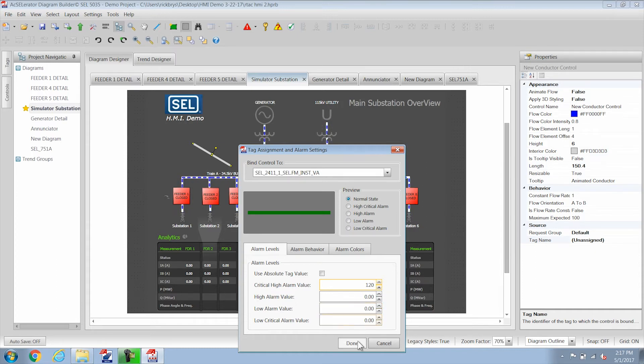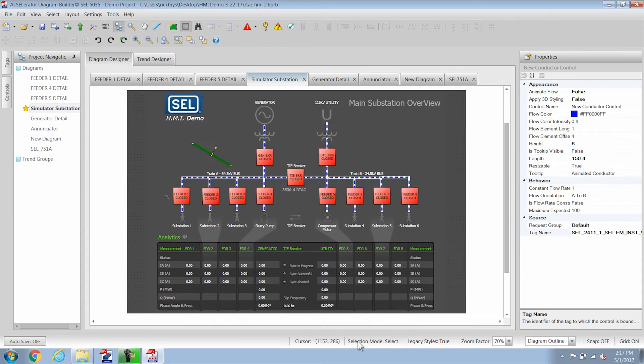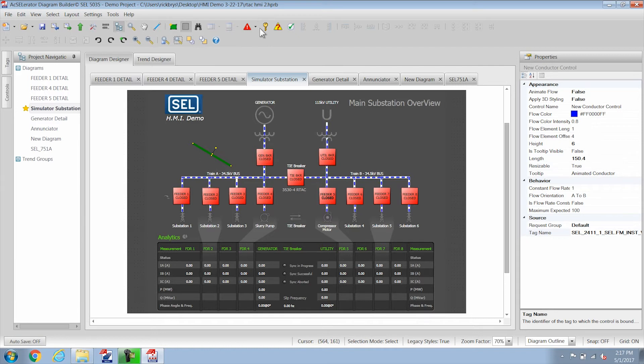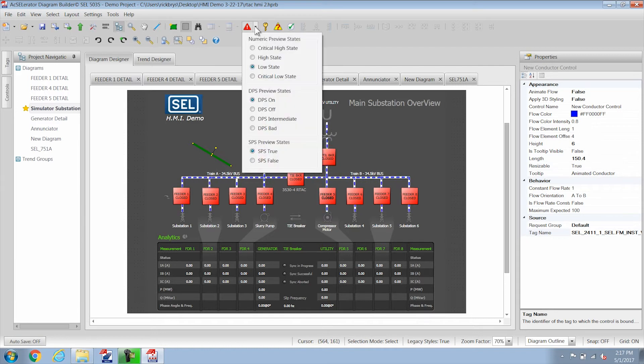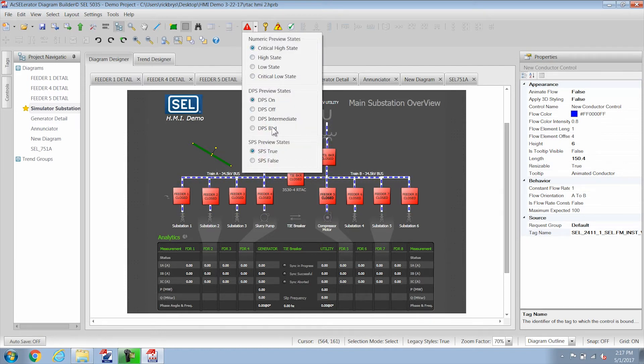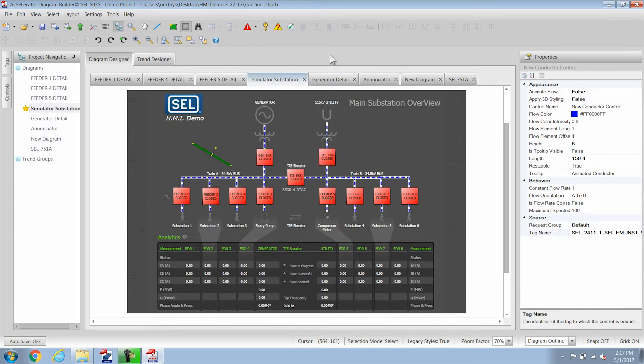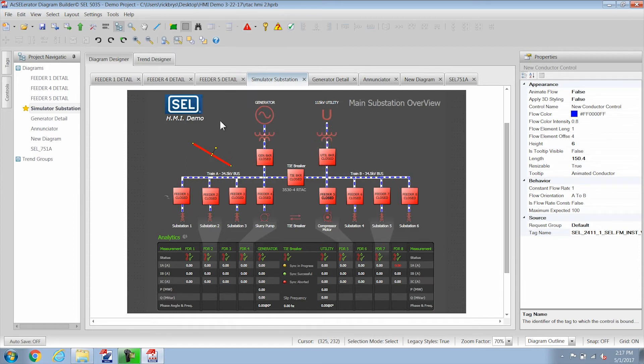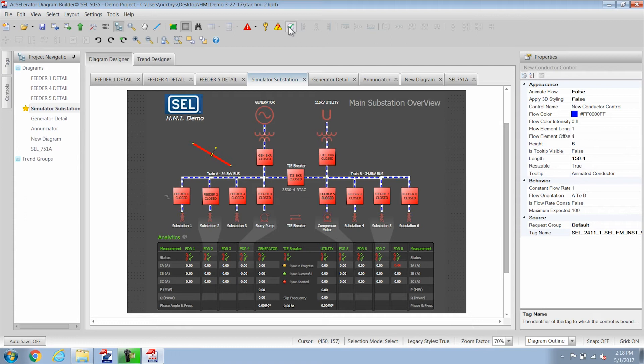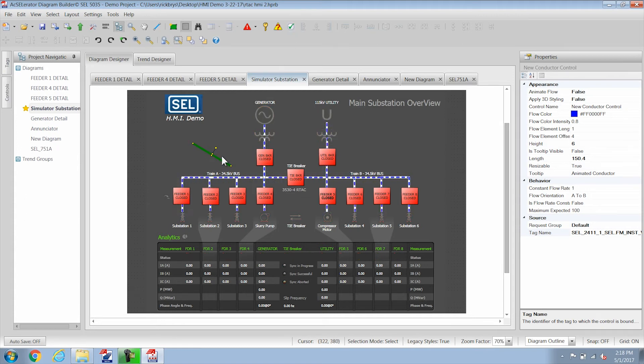So what's going to happen here, I'll click done and click on this simulation button up here at the top and on the simulation button you can actually look at what happens when you're having a real critical high state or an alarm state for status or whatever you want. So I click on that and you can see that the line turns red and clear it by clicking on this button and that's the normal state which is green. So on a conductor of course green is not normal but that's the way we set this up so you could do the opposite or you could have it animated.